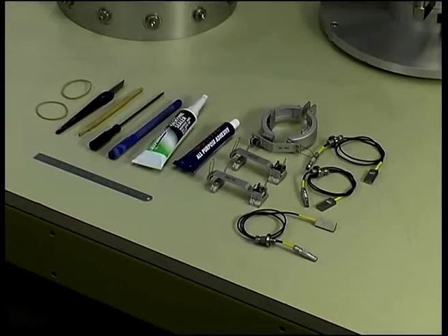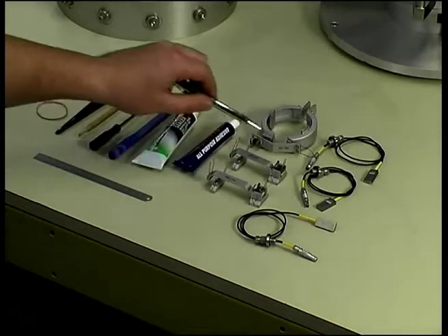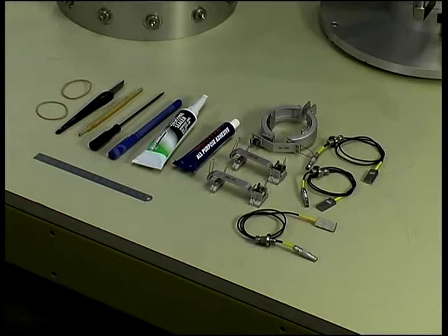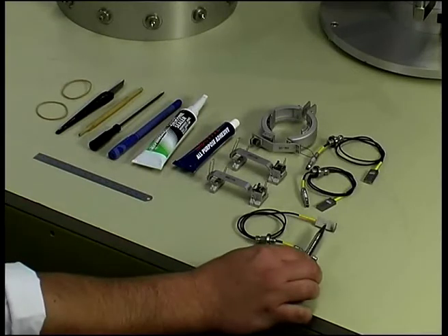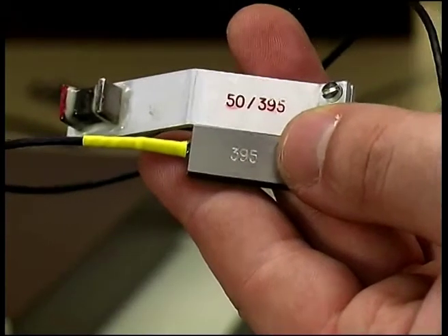A Hall Effect local strain set. Here we will be demonstrating a full 50mm set. It is important to check that the serial number of the Hall Effect chip matches that of the magnet as this is the pairing that was used for calibration.